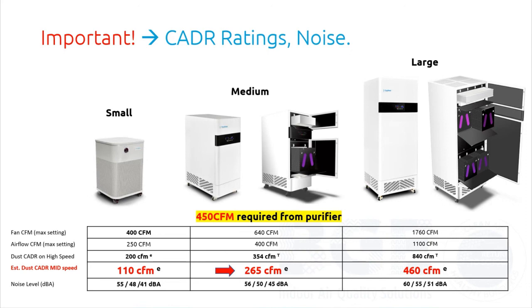Does UVC inside in-room units increase the power draw? Everything you add increases the power draw, yes definitely. So again, back to my point, it may be redundant if you believe the HEPA is already doing the job. I've seen air purifiers with a HEPA filter capturing 99.97%, but to make sure people buy it they add UV, ionization, photocatalytic — I saw one with four auxiliary additions. Those all add to the power draw and the cost. Better, in my opinion, to take your money and put it into one good quality unit.